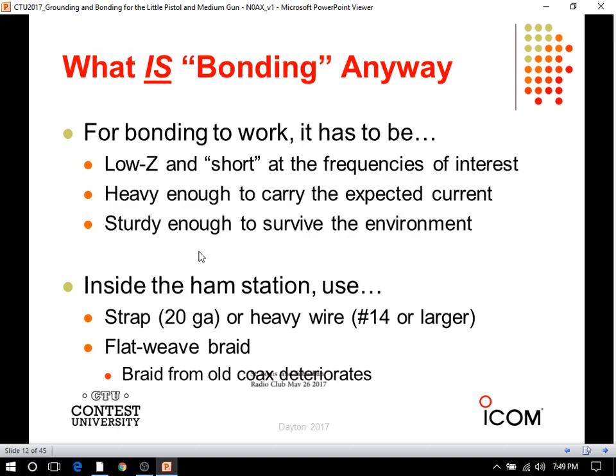That's what you want. They need to be heavy enough to carry the expected current. If we're just talking about an op-amp circuit, you may be able to use number 20 hookup wire, just little clip leads. That might be fine. If we're talking about something that's going to carry part of a lightning strike, if your tower gets hit, you need a much heavier conductor. You can see online all sorts of interesting videos of what happens to conductors when a lightning-sized current pulse hits them—they move and flap around. The force per foot can be hundreds of pounds with a kiloamp size pulse.